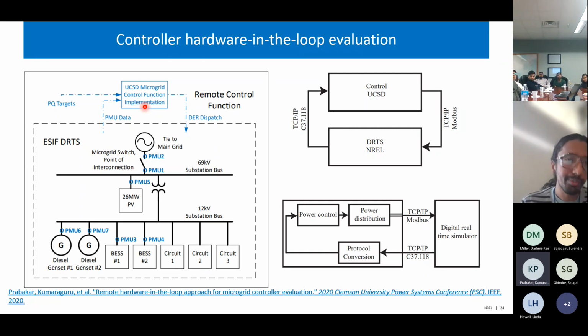If you think about it, this is how the real world also works. The PMUs are in the field, the controller is in the utility control center, and they exchange information either over general IP internet or through a dedicated connection. But the delays — usually around 120 milliseconds — are reasonable to assume as okay.